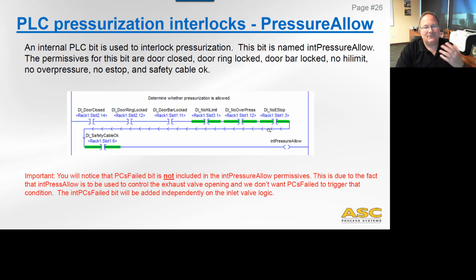Okay. Pressurization interlocks, again, very similar. There's a pressure allow, which is like the okay to pressurize relay of the hardwiring, and that is basically looking at door locked, the ring locked. Now here, because I want to make sure that not just the bar is in place, I'm going to put in that the door be closed, that the door limit switch is closed, and the ring is locked, and the bar is in place to get allowance of pressure. I'm also going to have no high limit, because we don't want a high temperature condition. We don't want an overpressure condition, and we don't want e-stop, and we want our safety cable okay. So all of these are tied into this pressure allow.